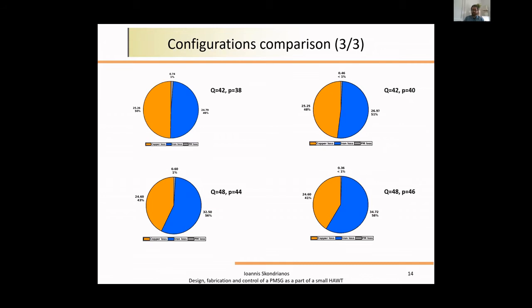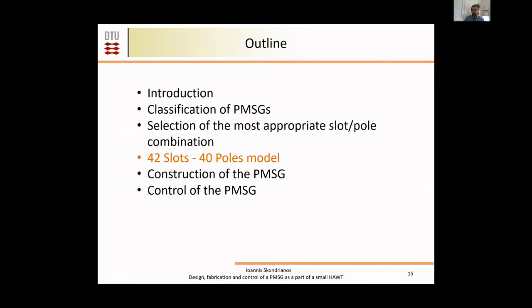This can be depicted in this slide too. The blue part of the pie is the iron losses. We can see again as the number of poles increases, the losses do so. Also, permanent magnet losses, the eddy currents on the magnets, are 1% or less of the total losses. Taking all this into consideration, we decided to go with a 42 slot and 40 pole model.